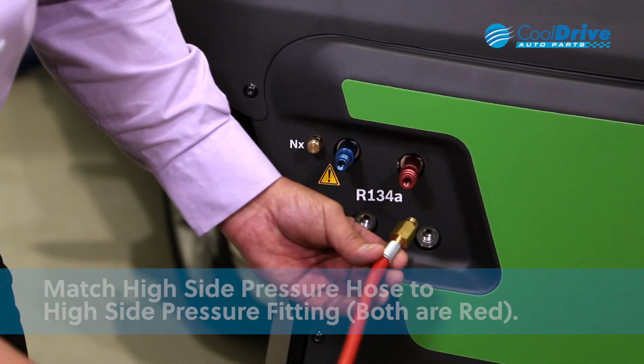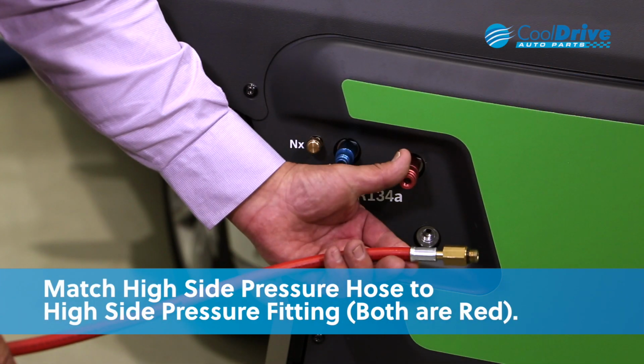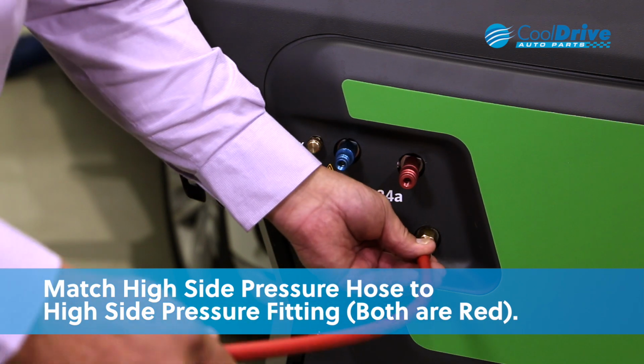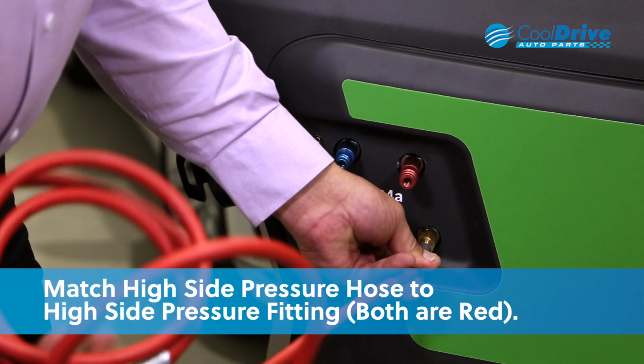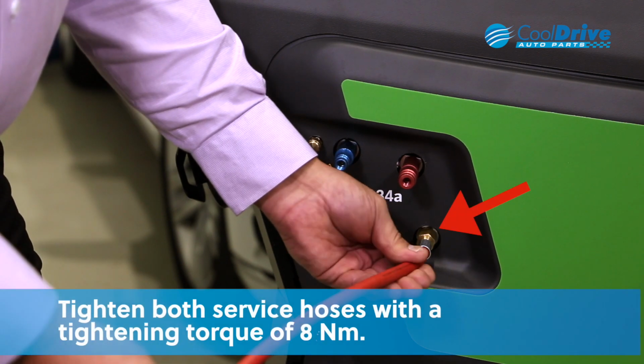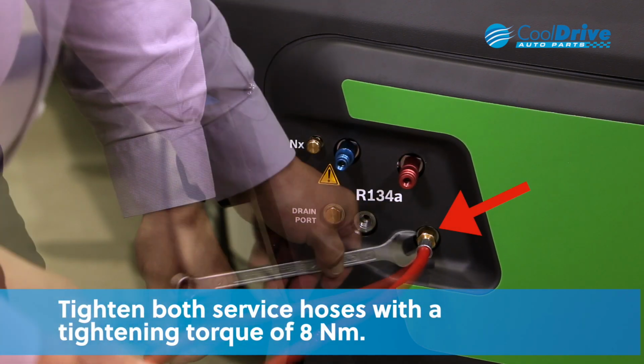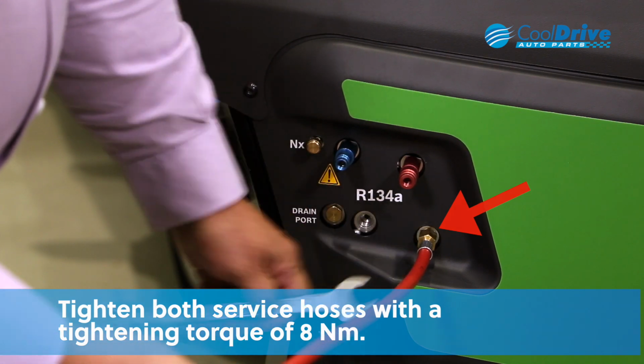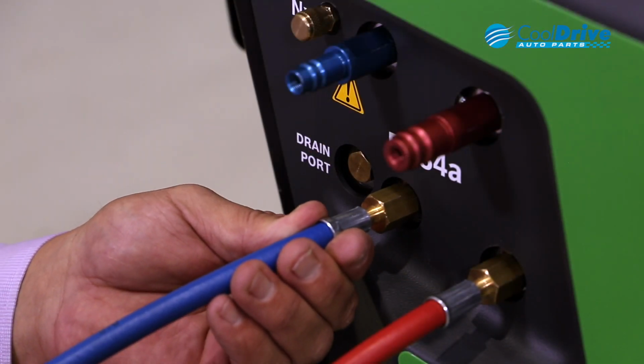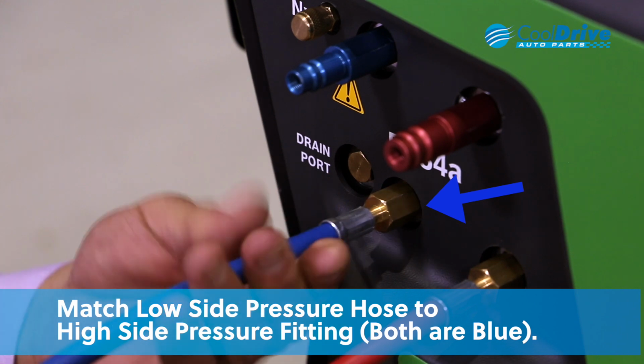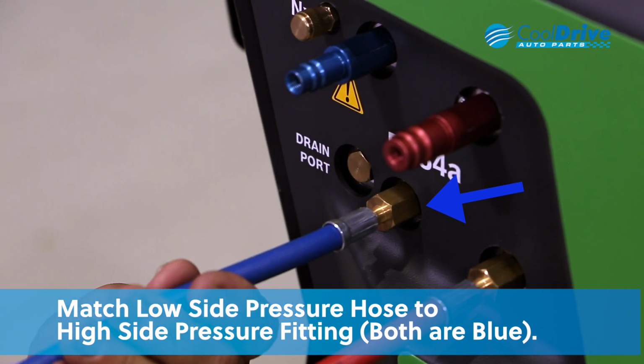Then it's simply a matter of matching our high pressure hose to our high pressure fitting and then screwing it into the actual correct port. Once we screw the fitting into the correct port, we tension it to around 8 Newton-meters until it's nice and firm. Then once the high side's fitting, just apply the low side hose fitting directly under the low side adapter.